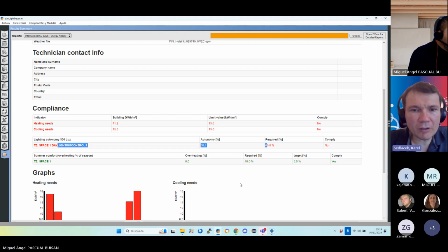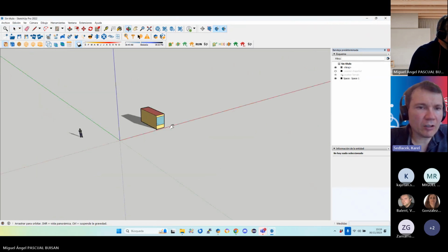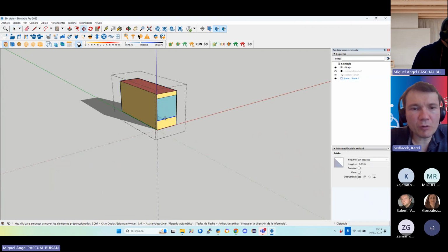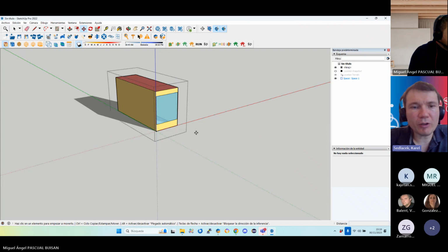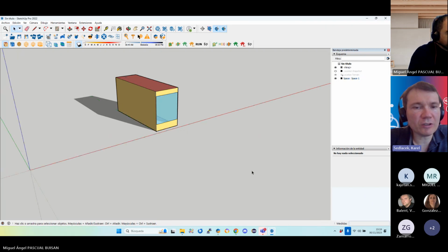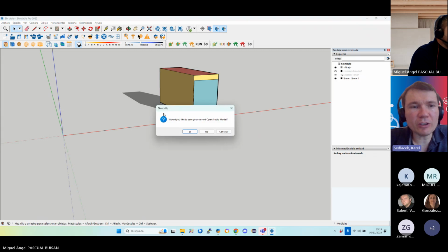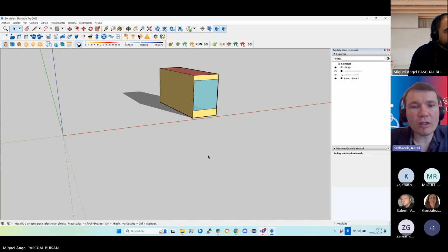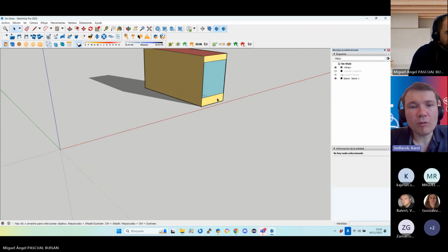I will just mention that for this calculation the envelope is not important, but only the results of the daylight calculation. If you have these not good numbers, it is because of the inside, and maybe you can also show the sensor inside, what it is doing and what we are using for the calculation. You can change the size of the window you already made, or put another window or a different kind of glass inside. So there are many options.